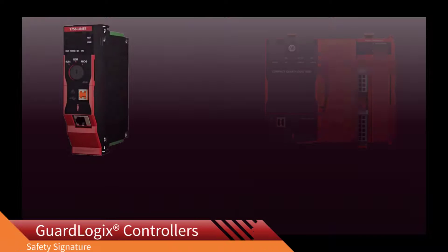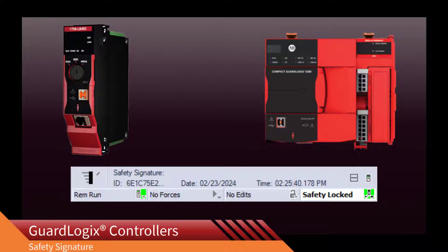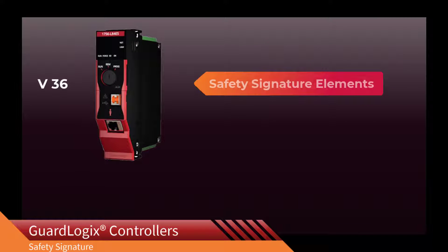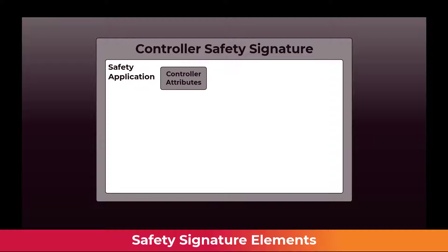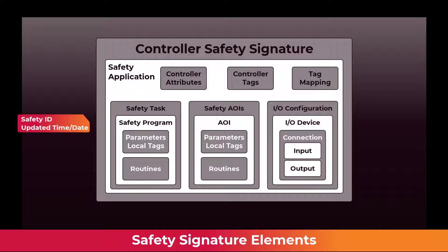The GuardLogix system uses a safety signature to verify the integrity of a safety application. GuardLogix version 36, released in 2023, introduced safety signature elements. Safety signature elements divide the GuardLogix safety controller signature into smaller pieces and assign each piece a safety ID and an updated time and date.